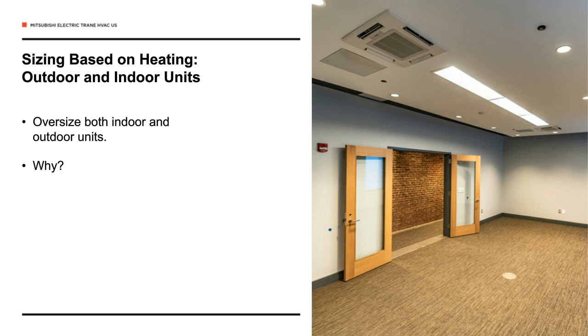As I mentioned earlier, I want to make sure that we oversize, if we're using this approach, not just the outdoor unit, because we can run into a situation where if our indoor units haven't been bumped up in size, the outdoor unit has more capacity, but the indoor units really can't pick it up, so to speak. So generally, you're doing both the indoor units and the outdoor units. And I always counsel engineers when they're using the selection software to look at it as an iterative process. Make a selection, look at the capacities, look at the discharge errors, go back and tweak it a little bit, play around with sizes. Maybe you bump a few indoor unit sizes up or bump the whole system size up. But look at it as an iterative process as you're designing to make sure that you're happy with the end result.